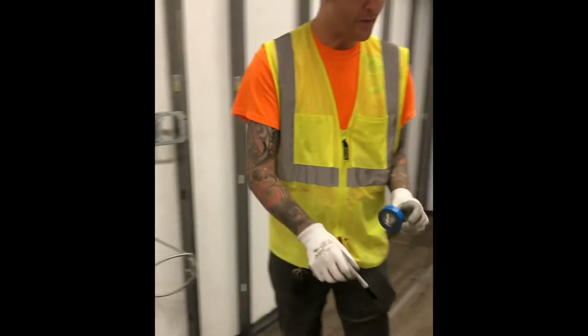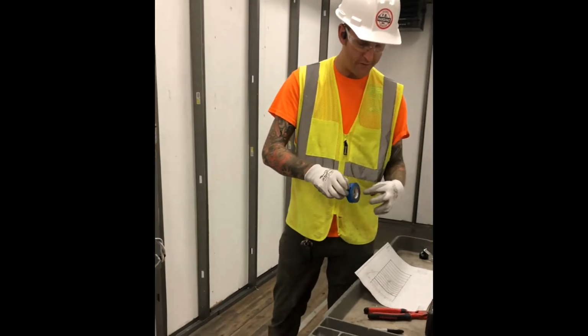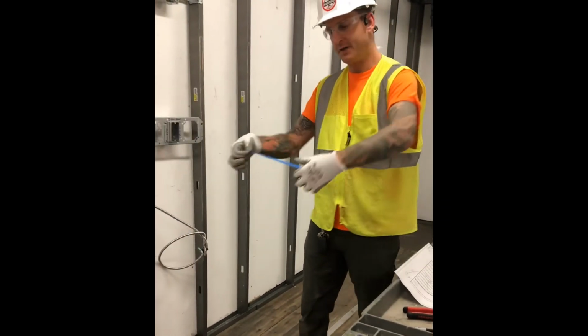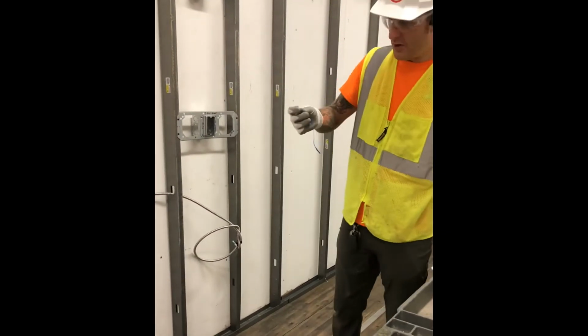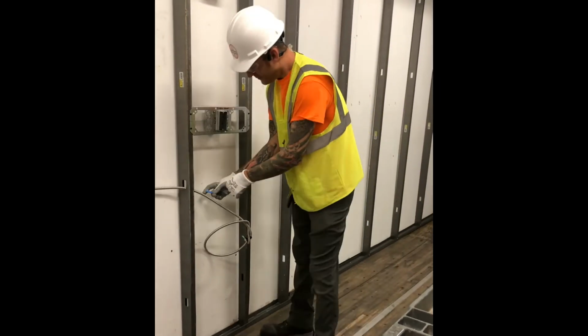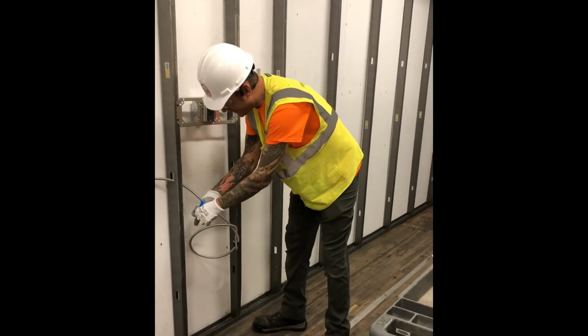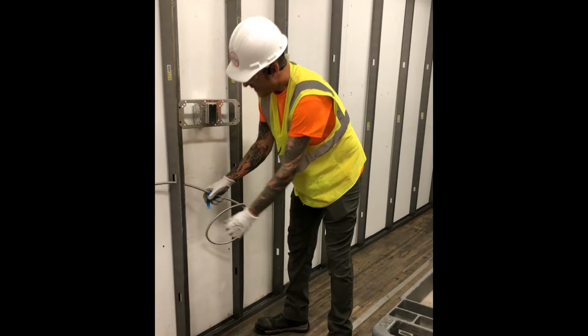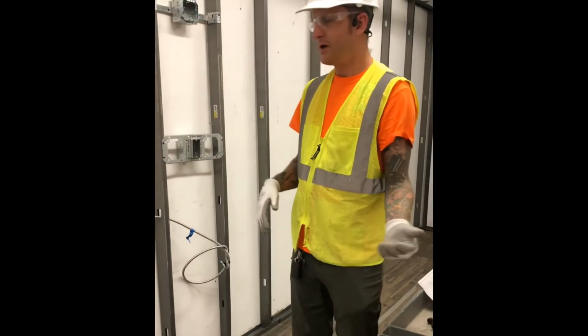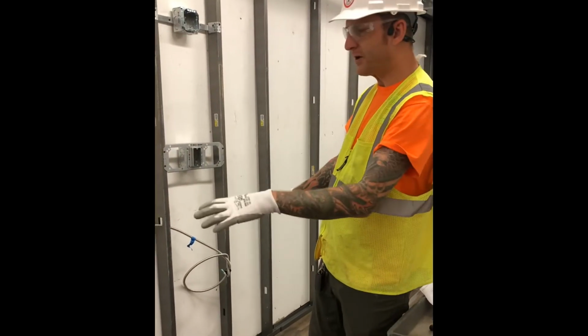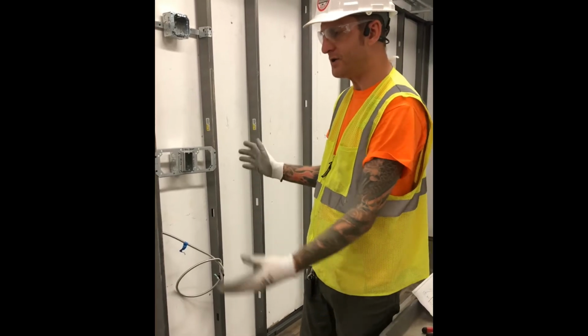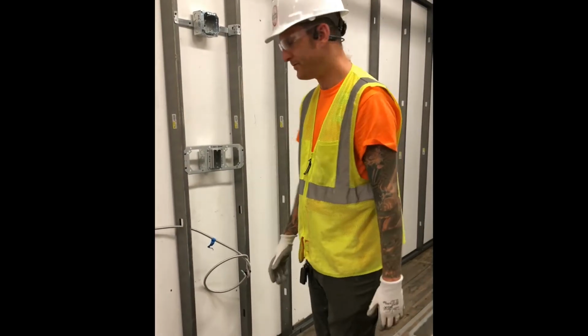That way, if someone comes back and has to finish where you left off, because you might get put on another task, break your tape a little bit longer than where you wrote it and wrap it around the cable like that. That way, no one needs to go back to the drawings. They already see that it's circuit 3, so it's a lot easier to just jump right back into the task.